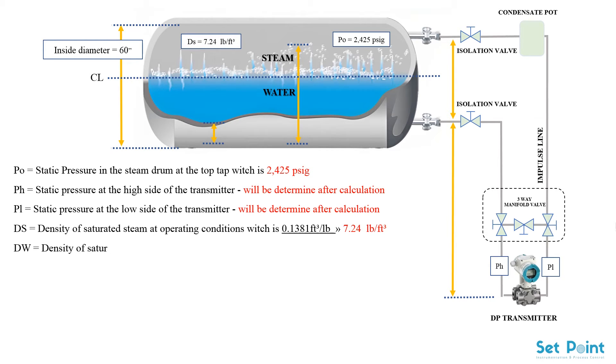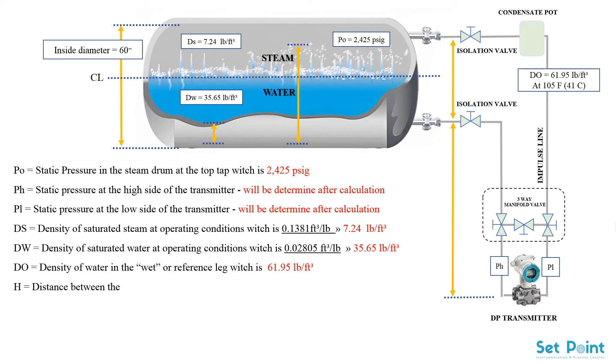DW equals density of saturated water at operating conditions which is 35.65 pounds per cubic foot. DO equals density of water in the wet or reference leg which is 61.95 pounds per cubic foot. H equals distance between the high and low drum taps which is 33 inches.